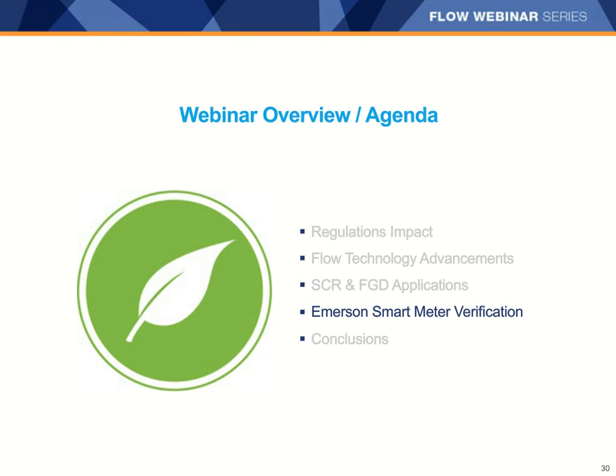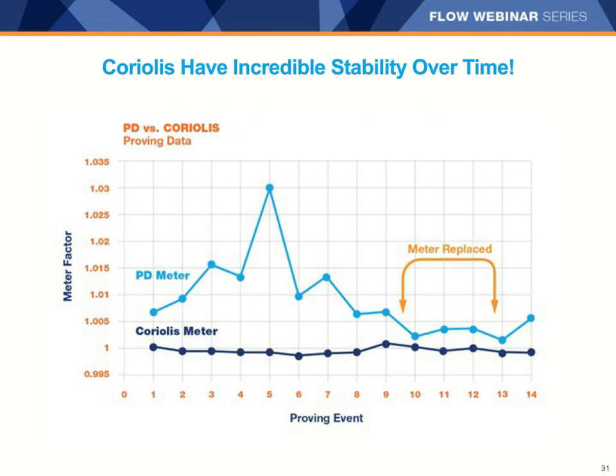Let's now look at Emerson's solution that can help save on calibration costs and provide even more reliability in your system. It's called Smart Meter Verification, or SMV. Coriolis meters have very good long-term stability and can reduce or eliminate unnecessary calibrations in many applications. The above graph details multiple proving events of a Coriolis meter and a positive displacement meter. You can see the reliability and repeatability of the Coriolis meter.